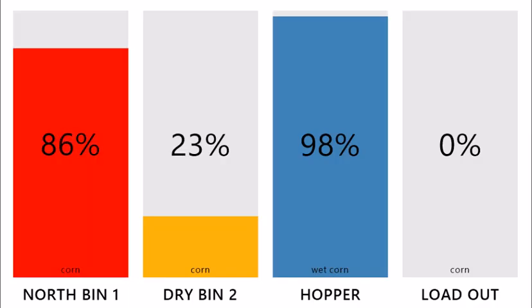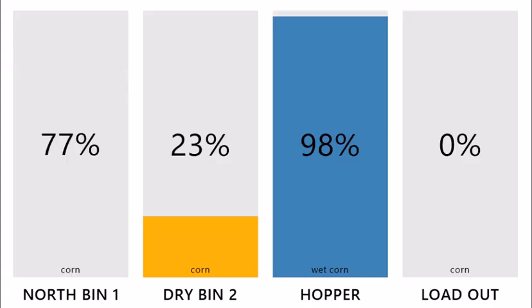If I decrease the bin's contents to 80%, notice that the alarm is still active. That's because our reset level is set to 70%. The fill bar will continue to blink red until we hit our reset level. And now that we've gone below that reset level, our fill bar is back to normal. We can now exceed 70%, and the alarm will stay inactive until we reach 80% again.